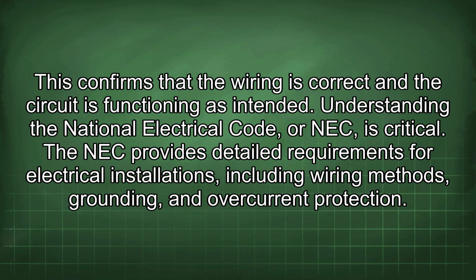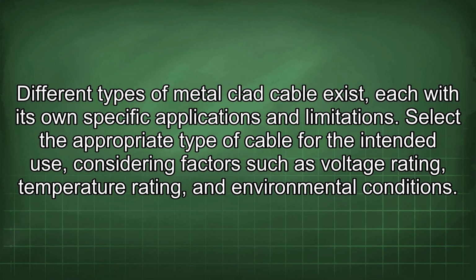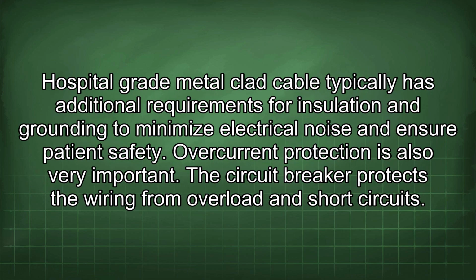Understanding the National Electrical Code, or NEC, is critical. The NEC provides detailed requirements for electrical installations, including wiring methods, grounding, and overcurrent protection. Different types of metal-clad cable exist, each with its own specific applications and limitations. Select the appropriate type of cable for the intended use, considering factors such as voltage rating, temperature rating, and environmental conditions. Hospital-grade metal-clad cable typically has additional requirements for insulation and grounding to minimize electrical noise and ensure patient safety.